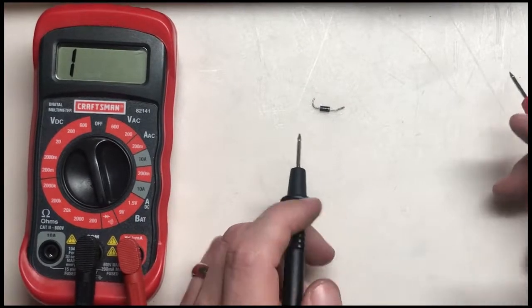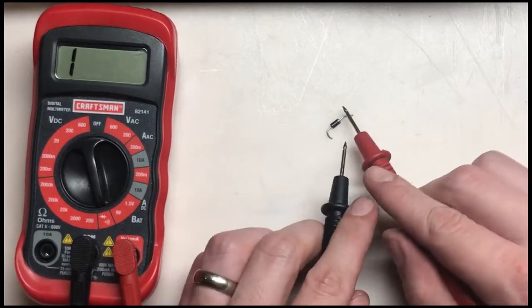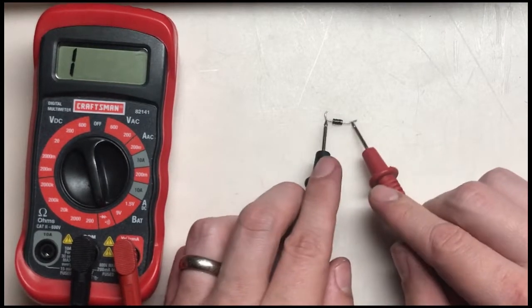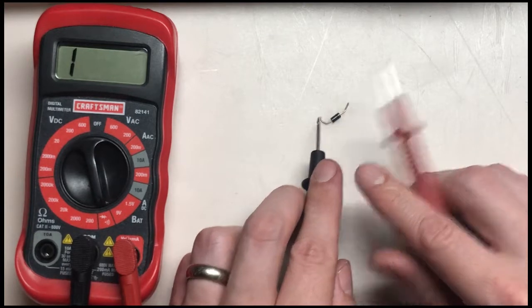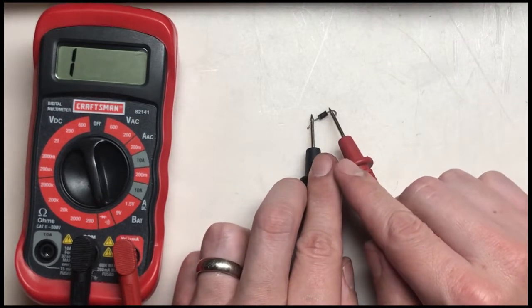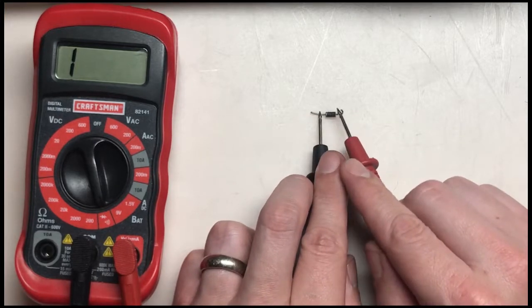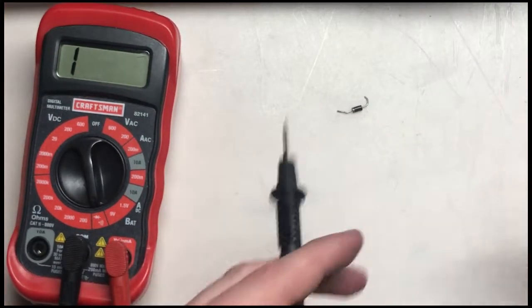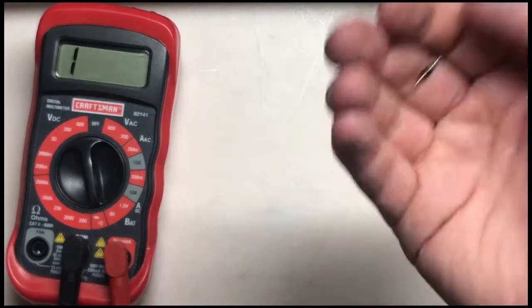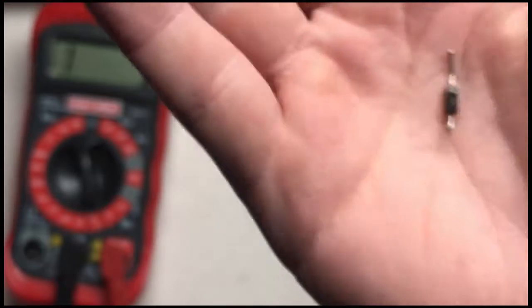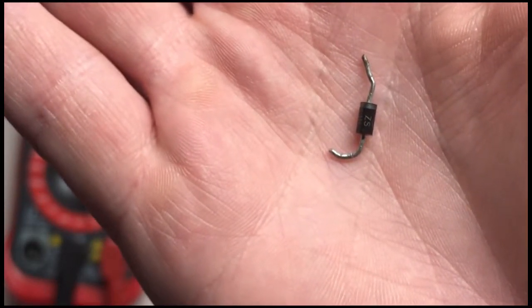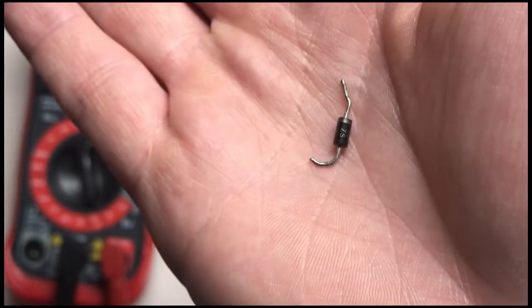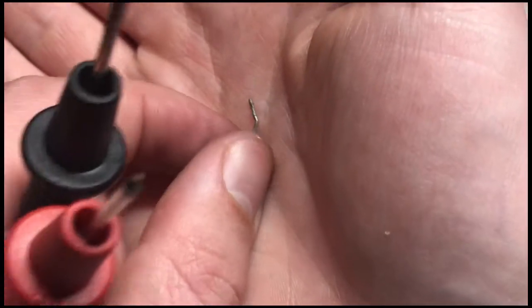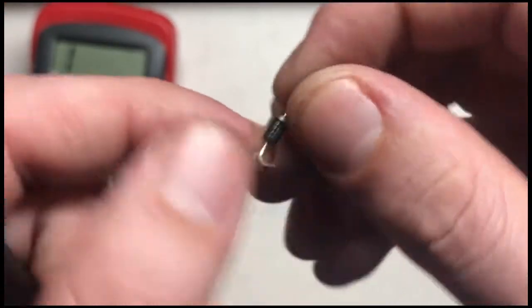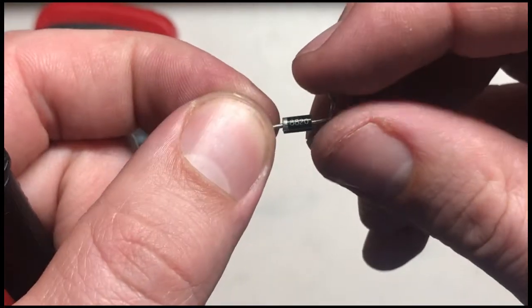All right, here's the diode out of circuit, so let's go ahead and test it. Get my meter on there. Okay, we're fully open there. Fully open in both directions. So this diode is confirmed dead. So that's killing our minus 15 volts, which may be the complete cause of our issue, which would be great. I don't believe I have one of these in stock, so I'm going to have to order it. But when I get it in, I will replace it, and we'll see if I have our minus 15 and got rid of our sweep issue.